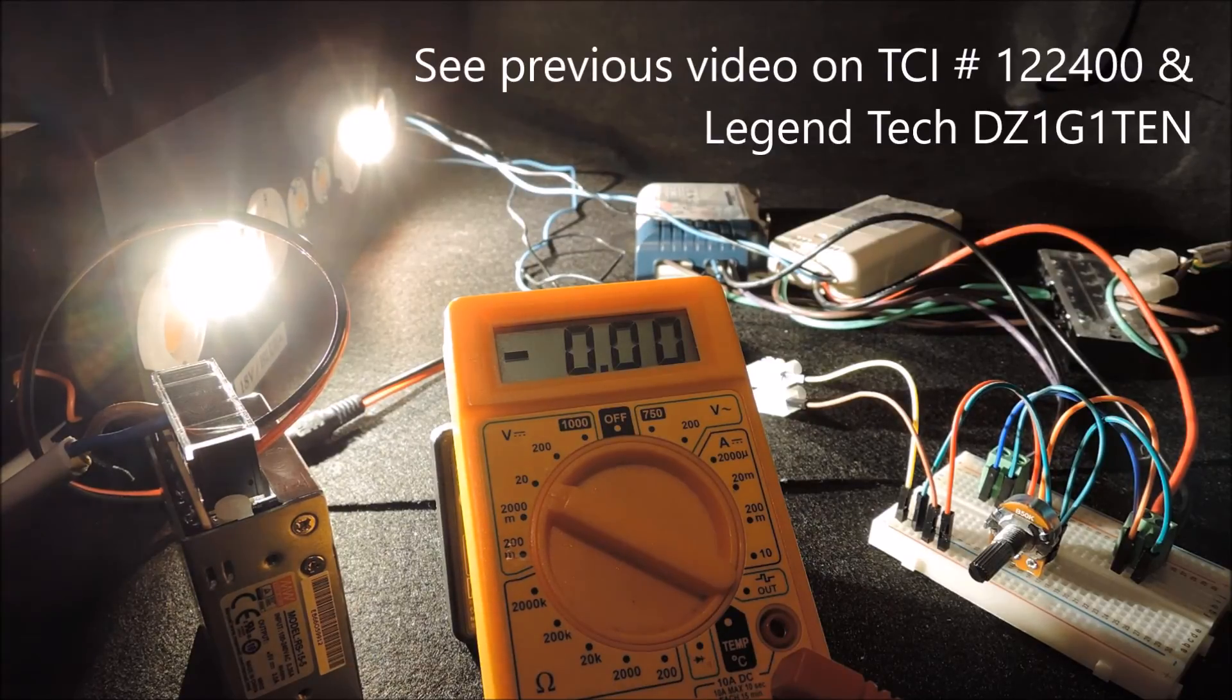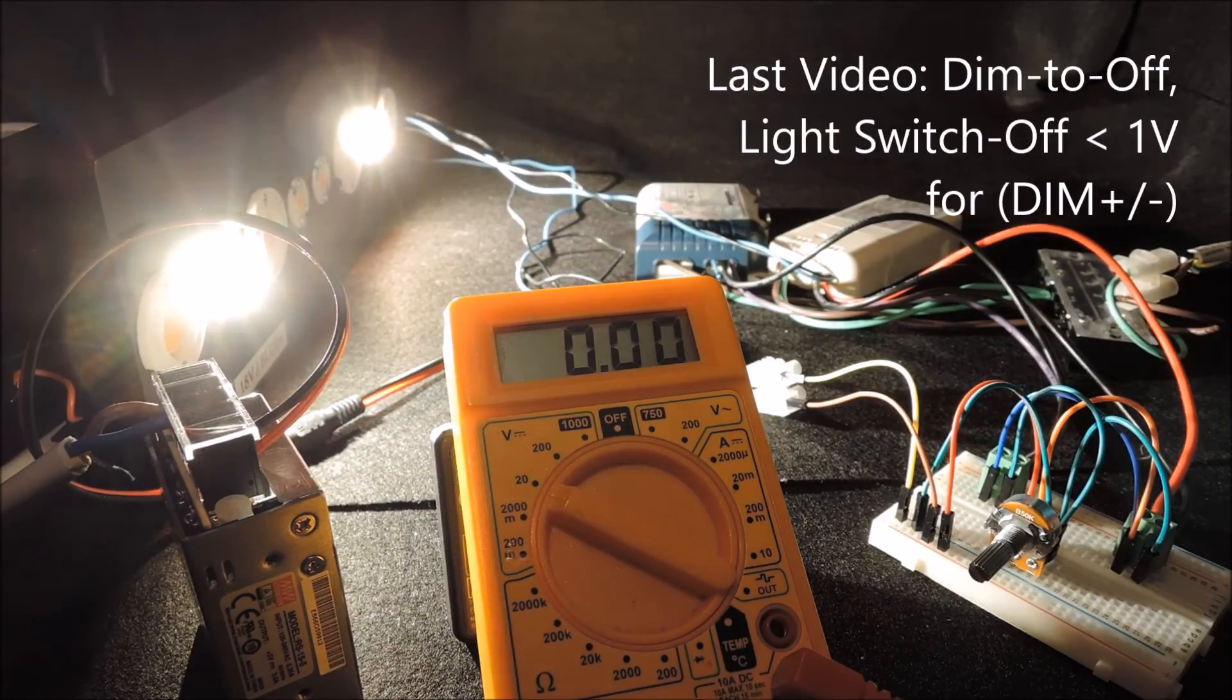In this video, we used the TCI DC Mini Jolie 122400 with the Legend Tech DZ1G1TEN controller to show that the driver would switch off the light when we hit below 1 volt across the dim plus or minus input for the driver.